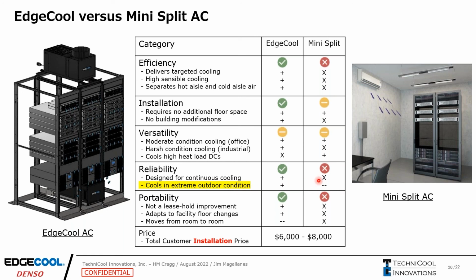Our reliability, we're designed for continuous cooling year-round, 24/7 operation. Mini split systems are comfort cooling, so they're mainly designed for summer months and not 24/7, 365 days a year. We're cooling in extreme outdoor conditions, really low temperatures. So Minnesota, if the outside temperature is -10 degrees, we're cooling down that no problem because our condenser unit's inside the building. Sometimes the mini split systems have issues with that. Portability, not a leasehold improvement. We move on the factory floor. We can move once the lease is up. So mini split systems just don't have that benefit to them.